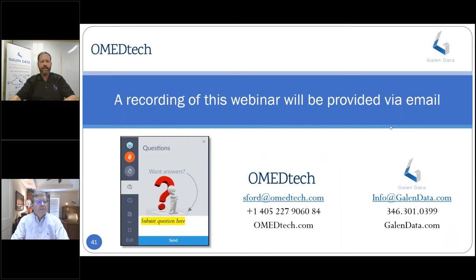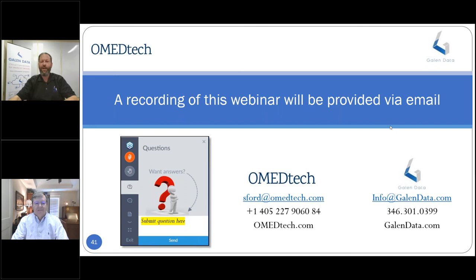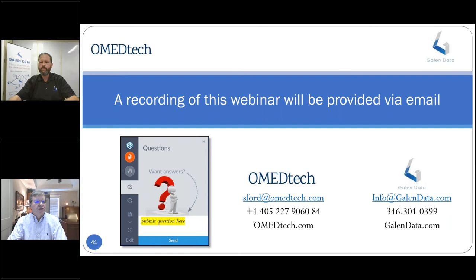On to the Q&A. An audience member asks: earlier in the webinar you talked about if you have the CE mark, you're assured of having an unannounced audit once every five years. Is there any warning at all, or do they simply show up? They simply show up — they knock on the door and say 'I'm here to audit you.' You typically have to sign an agreement with notified bodies that you're going to be ready for unannounced audits as part of getting your CE or EC certificate.